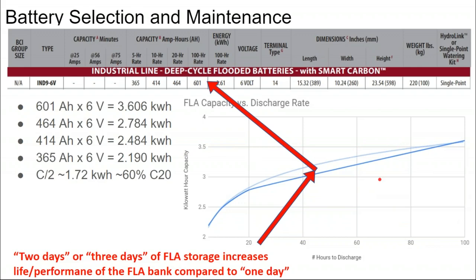So with a 100 hour discharge rate, if you had 5 days worth of battery storage, your average discharge rate might be C/100. On a day-to-day basis, your home load is going to be at 1 kilowatt at times, and at other times at 10 kilowatts. So if you have a 100 kilowatt hour battery and your home load is at 1 kilowatt, you're discharging at the 100 hour rate, and your battery bank actually has more storage capacity at that 100 hour rate than when your washer or dryer kicks on and puts heavier demand on the battery.